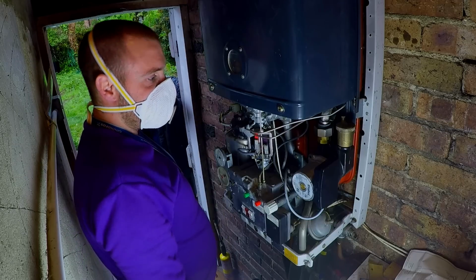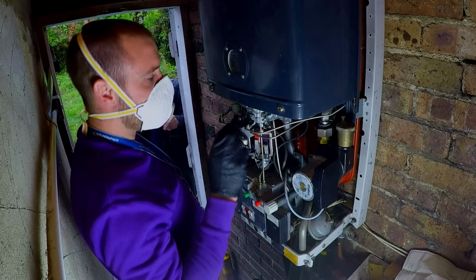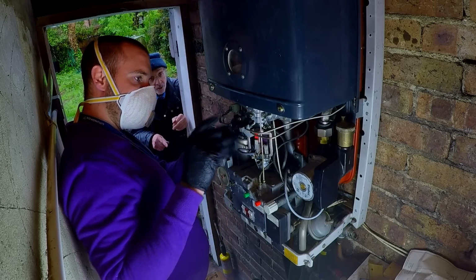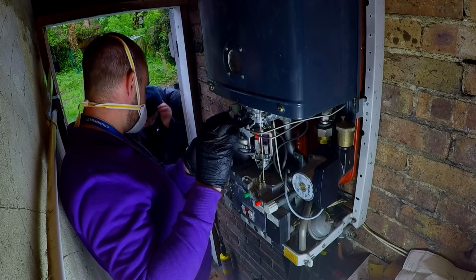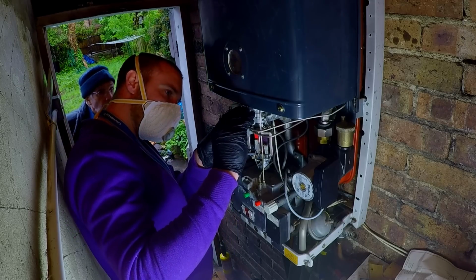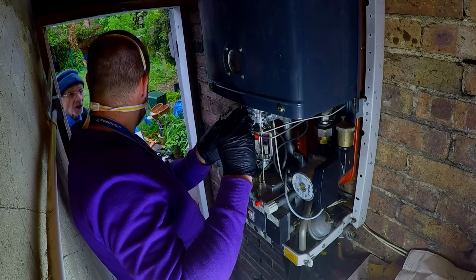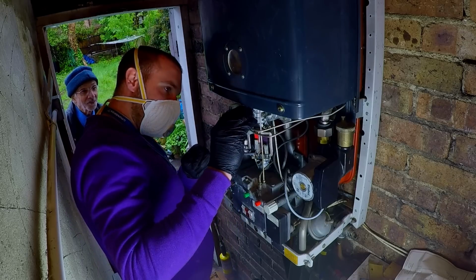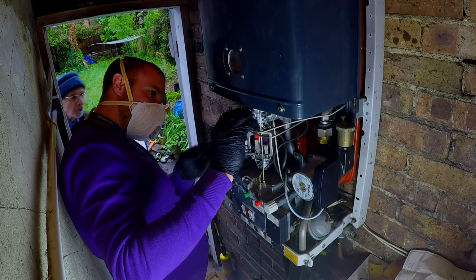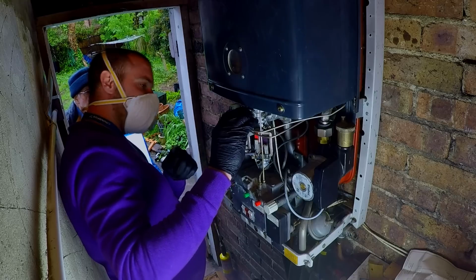Is it a plug or a gas valve? That's the gas valve. This is the water section. This is a servo valve, but this is what turns the gas on and off. Ah, okay, all right. But this is jammed as well. It's a governor, like. This big piece, that's the governor. But this should not be sticking out once it's removed. It should be in.